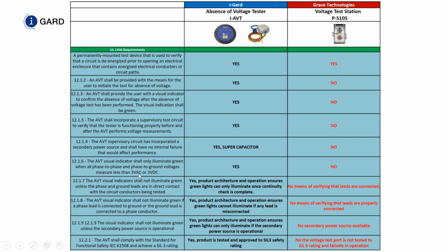We check for voltage if it's less than 3 volts AC or 3 volts DC. Yes, and you need to verify what is low enough using the voltmeter before you can enter the gear. The absence of voltage indicator shall not illuminate green unless the phase to ground leads are in direct contact with the circuit conductors. We monitor those phase conductors and we ensure that they are truly connected to the bus and we have a complete path before we indicate all green and it's safe to enter.